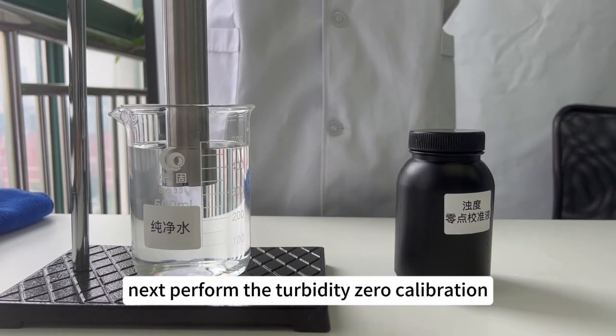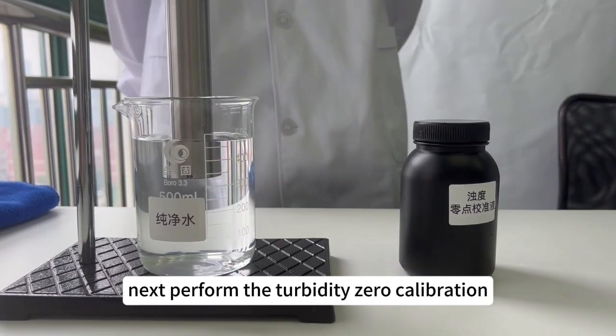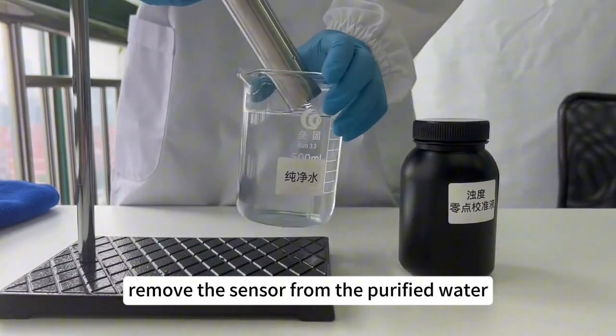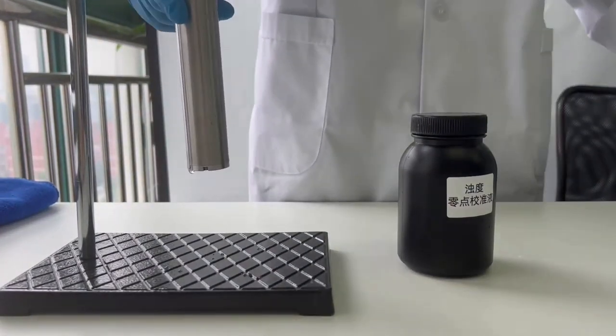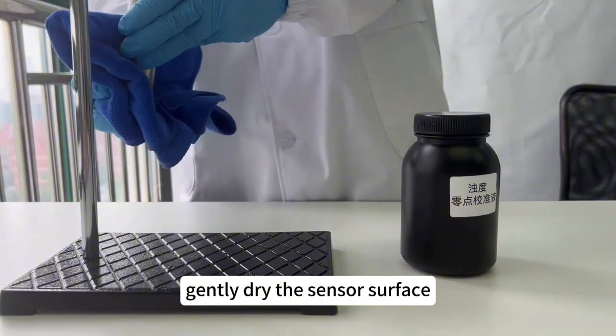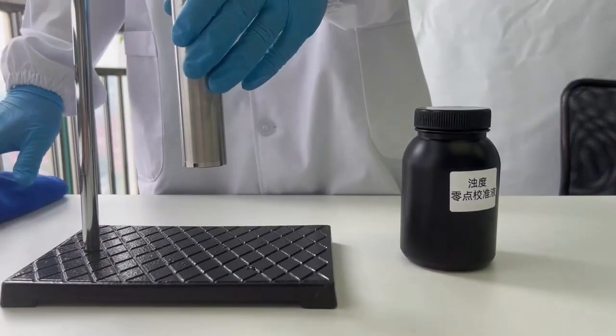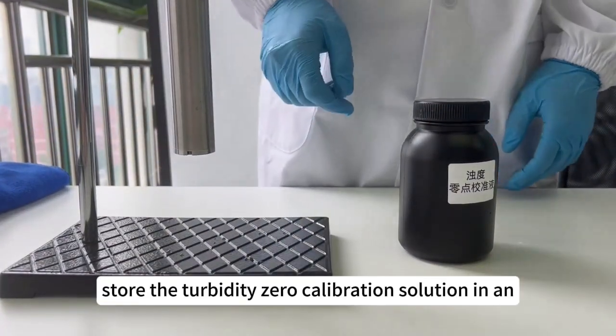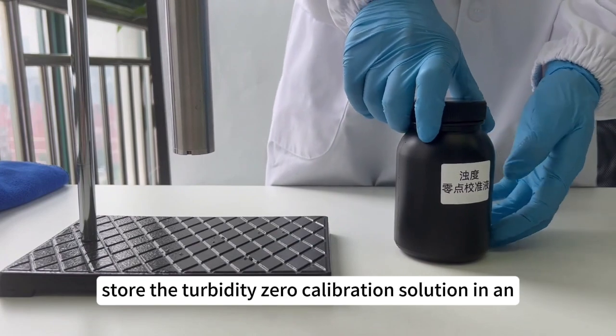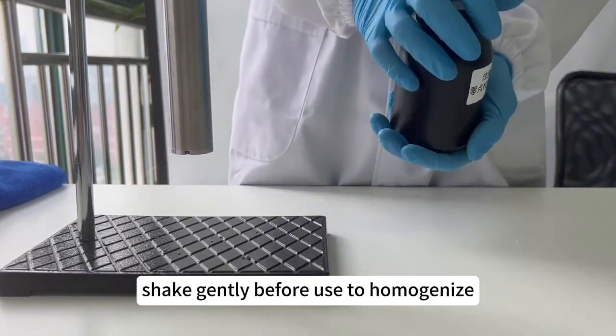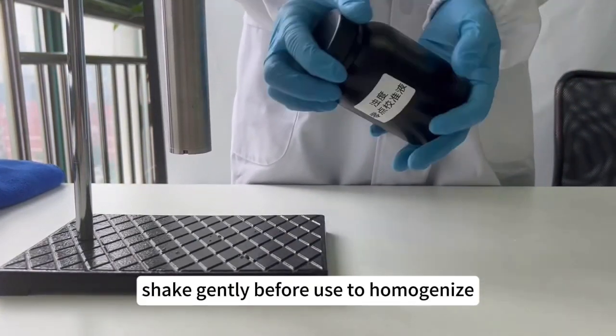Next, perform the Turbidity Zero calibration. Remove the sensor from the purified water. Gently dry the sensor surface. Store the Turbidity Zero calibration solution in an opaque container. Shake gently before use to homogenize.